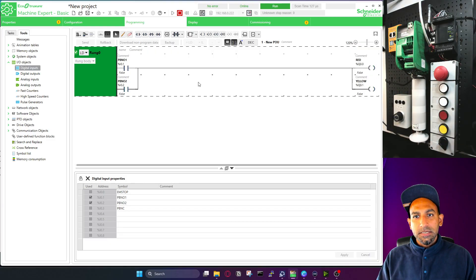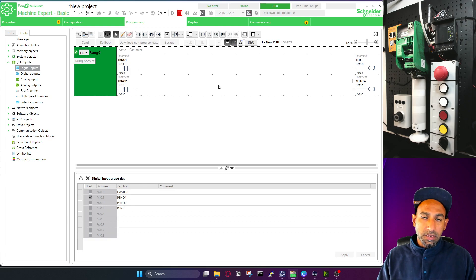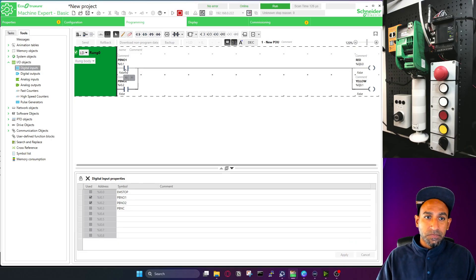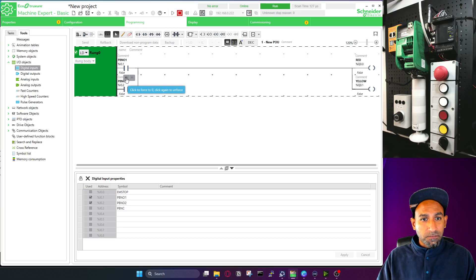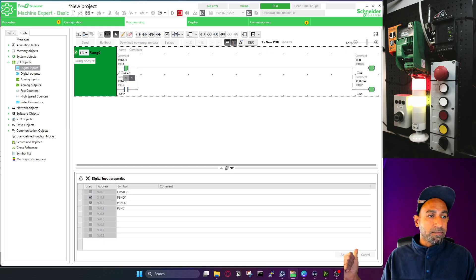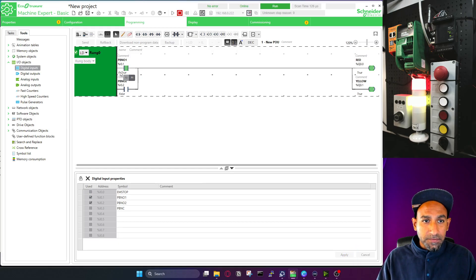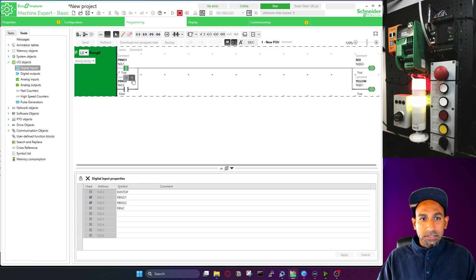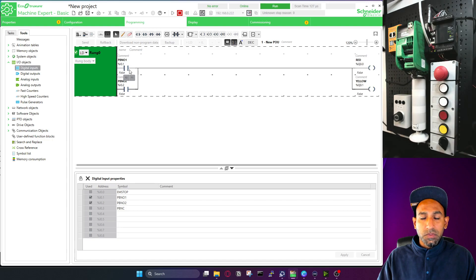Now a very interesting part: if you want to force the inputs and outputs — in case you don't want to turn on from the outside but want to force it from the software — you can do that. When you take your mouse there, you will see F0 and F1, which are force false and force true. If I take F1, you can see it's true, but I did not press the button. The F is shown here because this is forced.